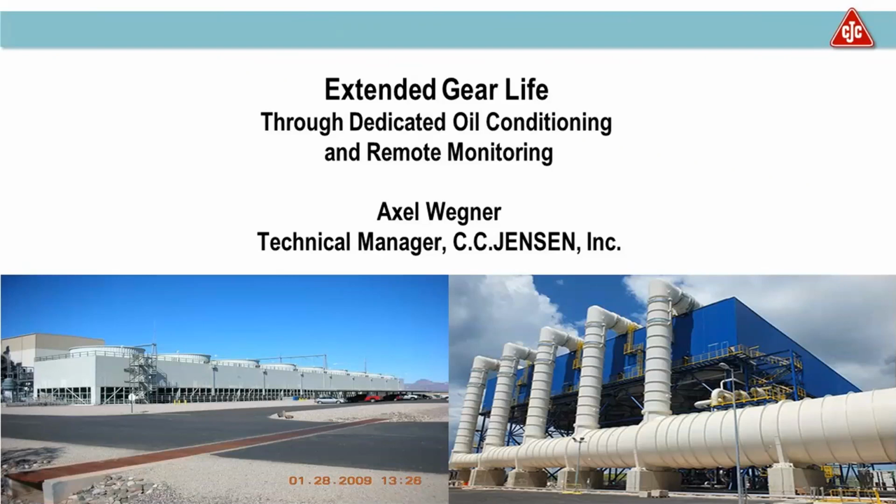Axel, I have a question about, have you had the chance to select or test online continuous monitoring and filtration of a gearbox on the ACC versus intermittent filtration, say 3-4 days, and then you move to another gearbox and do 3-4 days and come back, say 3 months from that and start all over again. What's your experience data that you may share with us here?